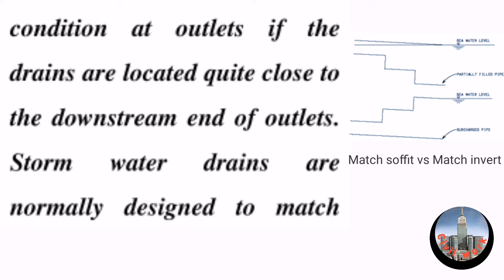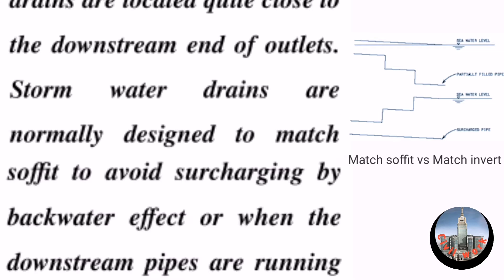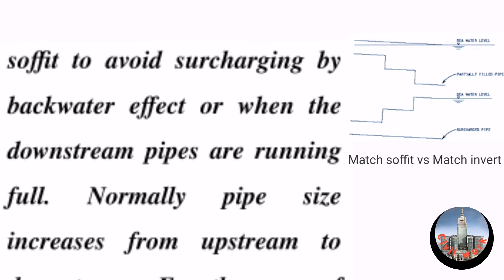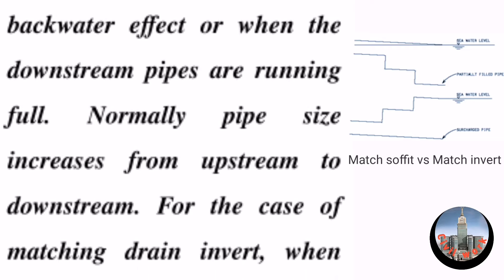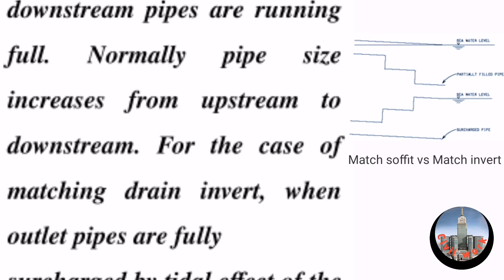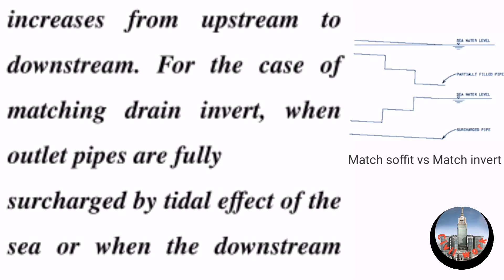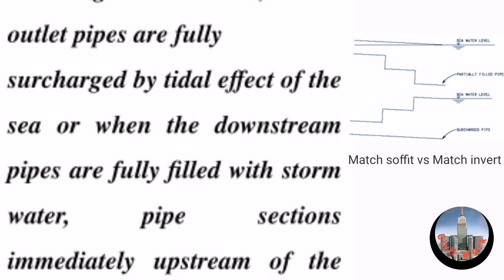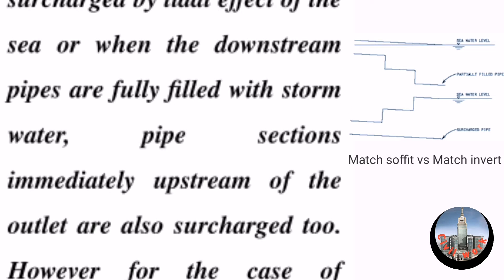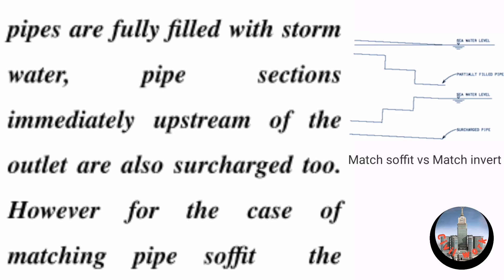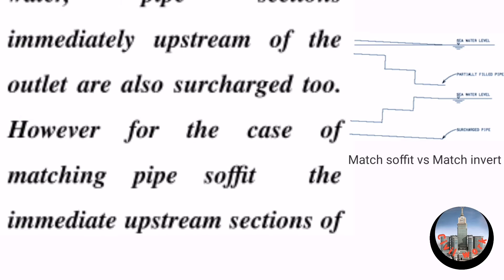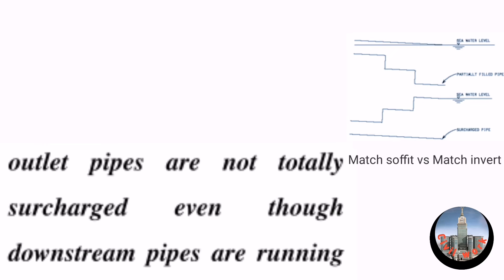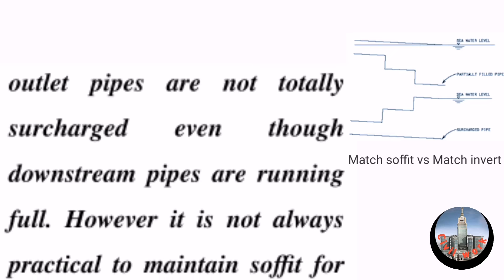Stormwater drains are normally designed to match soffit to avoid surcharging by backwater effect, or when the downstream pipes are running full. Normally pipe size increases from upstream to downstream. For the case of matching drain invert, when outlet pipes are fully surcharged by tidal effect of the sea or when the downstream pipes are fully filled with stormwater, pipe sections immediately upstream of the outlet are also surcharged. However, for the case of matching pipe soffit, the immediate upstream sections of outlet pipes are not totally surcharged even though downstream pipes are running full.